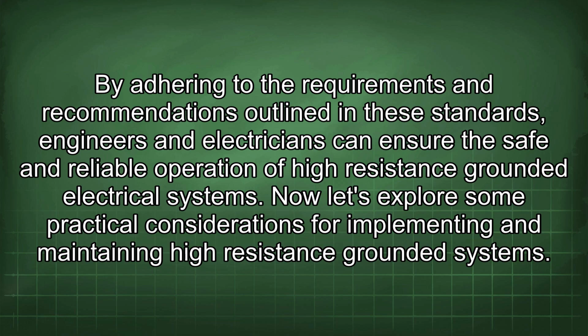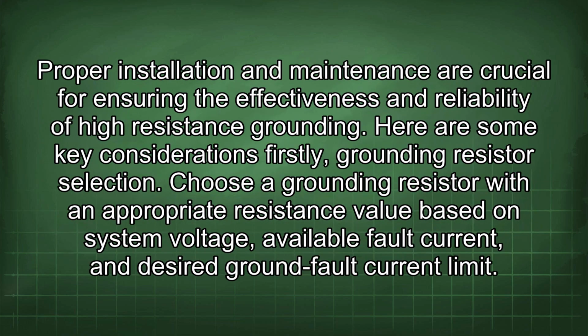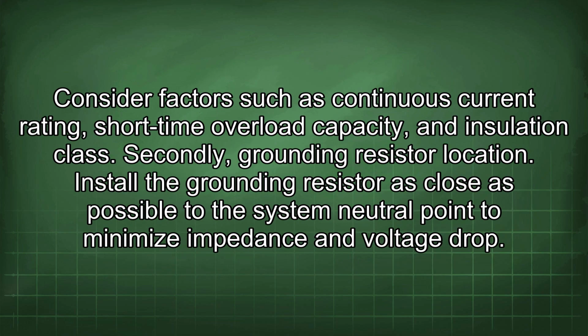Now let's explore some practical considerations for implementing and maintaining high-resistance grounded systems. Proper installation and maintenance are crucial for ensuring the effectiveness and reliability of high-resistance grounding. Here are some key considerations. Firstly, grounding resistor selection. Choose a grounding resistor with an appropriate resistance value based on system voltage, available fault current, and desired ground fault current limit. Consider factors such as continuous current rating, short time overload capacity, and insulation class.